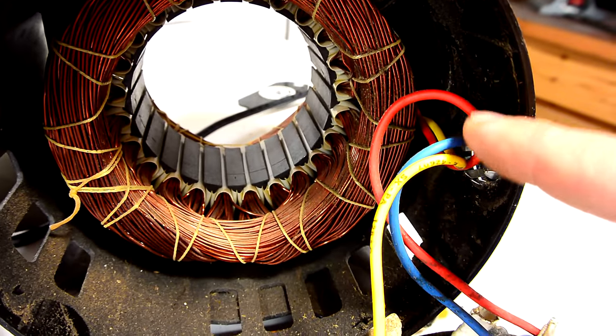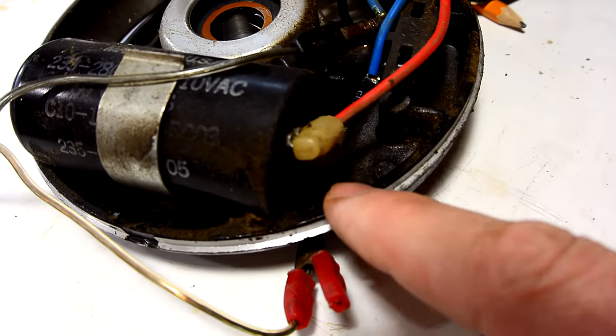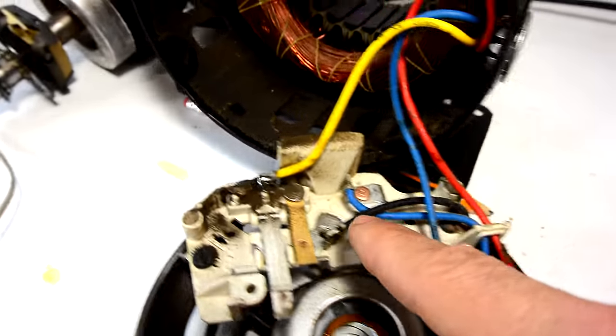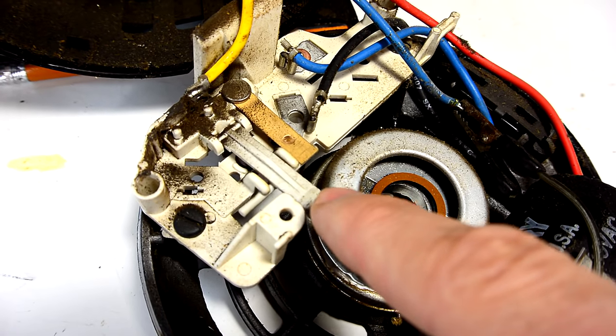One end of the starter winding is connected to this red wire and that goes to this capacitor and then the other side of this capacitor goes through this black wire onto here and that's the starter switch and that gets disconnected once the motor's up to speed.